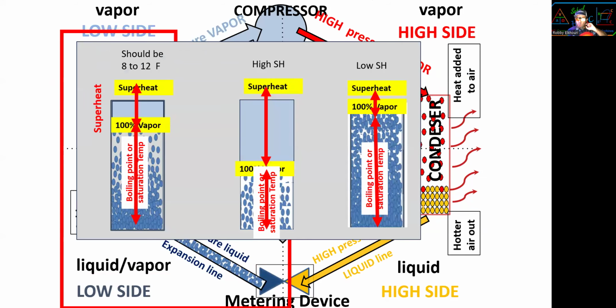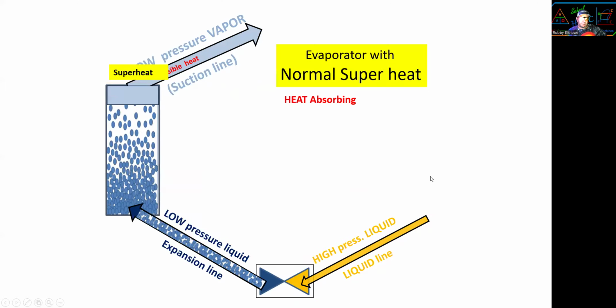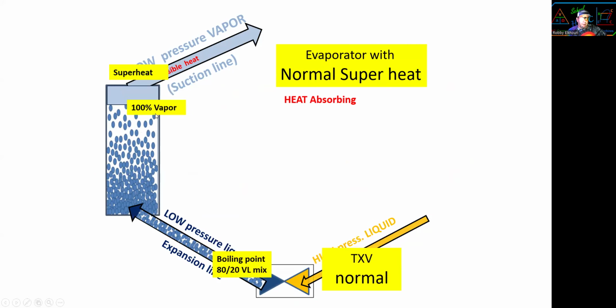Now, low side, let's talk about how it should be. What happens when we have high superheat? What happens when we have low superheat? Normal superheat: the heat absorption is normal. The TXV is normal, boiling at 80/20, 100% vapor towards the end of the evap. Perfect.